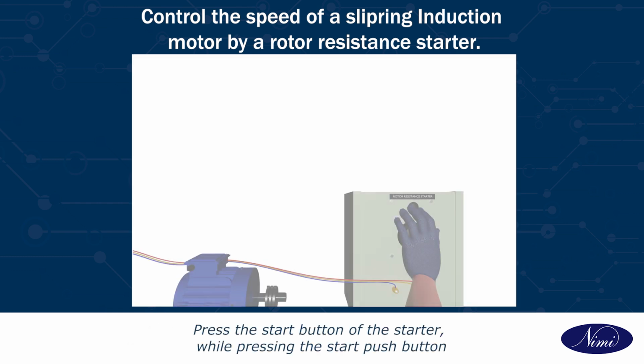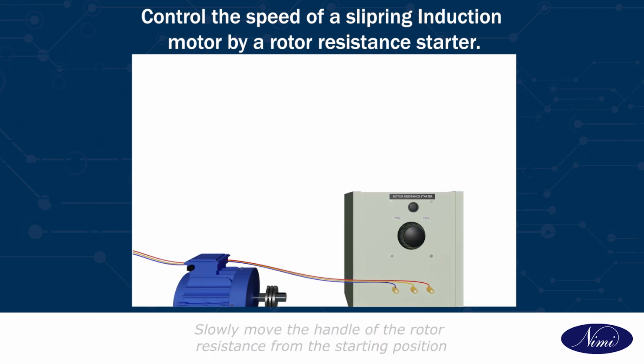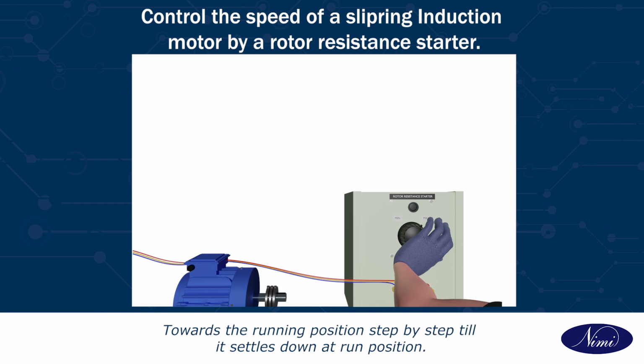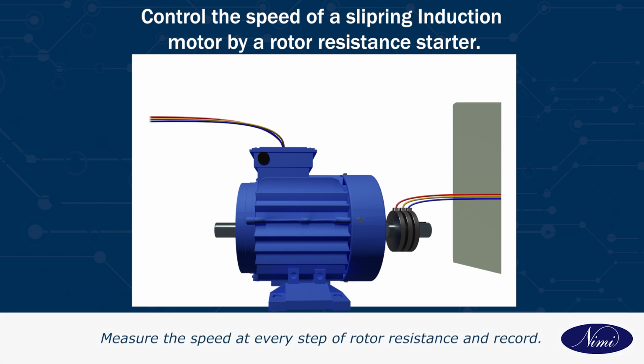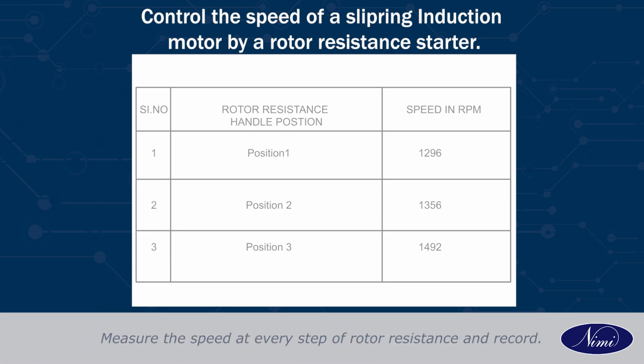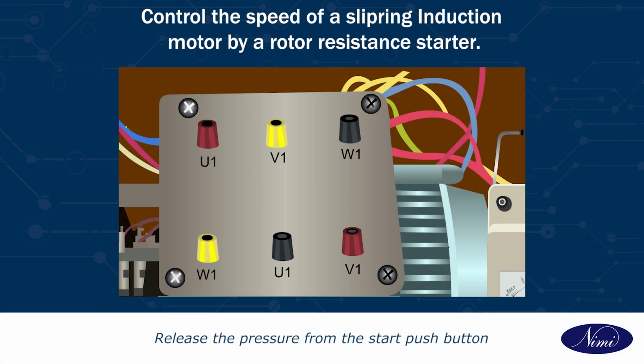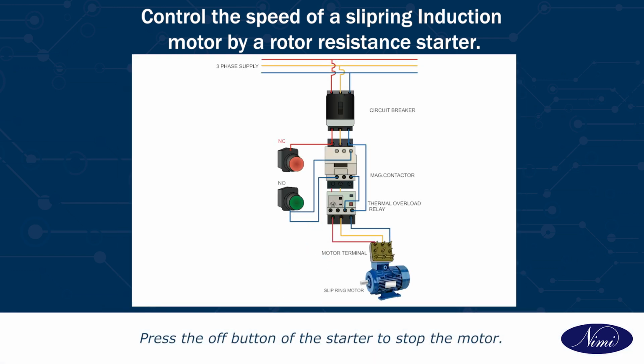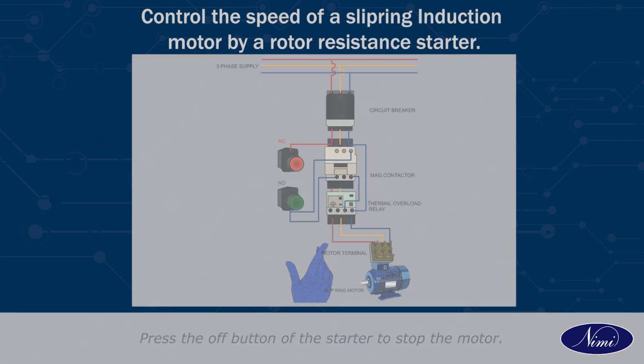Press the start button of the starter. While pressing the start push button, slowly move the handle of the rotor resistance from the starting position towards the running position step by step till it settles down at run position. Measure the speed at every step of rotor resistance and record. Release the pressure from the start push button. Press the off button of the starter to stop the motor.